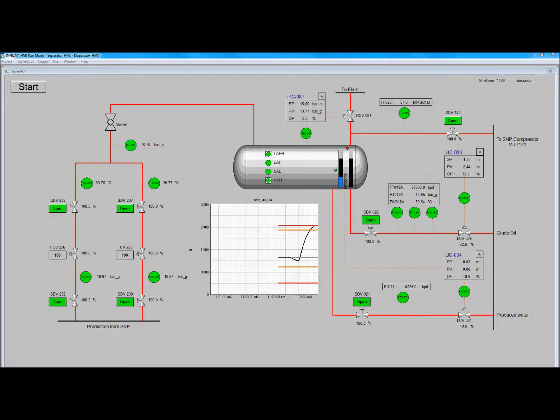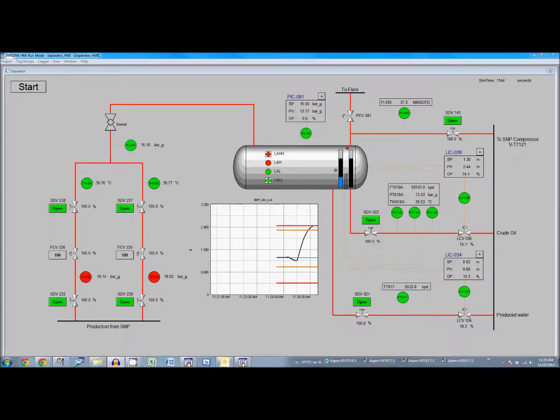Alright, that's LAHH. We assume at this point that the level continues rising. LAHH trips the plant, shutting down operations. Game over. Let's stop the simulation.